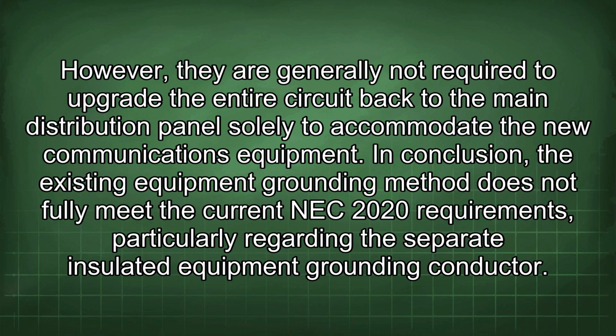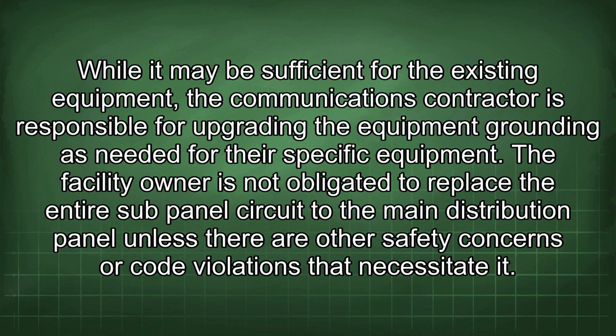In conclusion, the existing equipment grounding method does not fully meet the current NEC 2020 requirements, particularly regarding the separate insulated equipment grounding conductor. While it may be sufficient for the existing equipment, the communications contractor is responsible for upgrading the equipment grounding as needed for their specific equipment. The facility owner is not obligated to replace the entire sub-panel circuit to the main distribution panel unless there are other safety concerns or code violations that necessitate it.